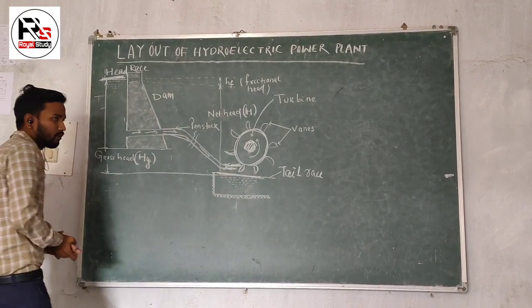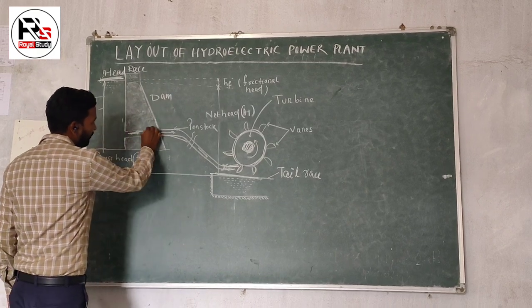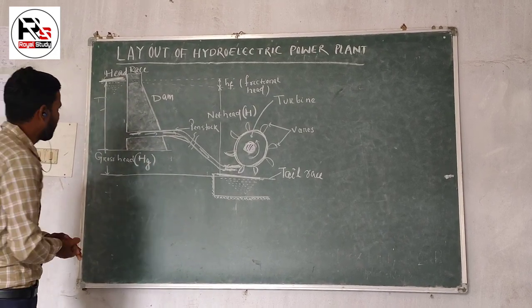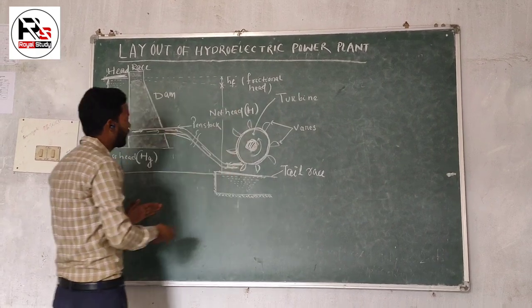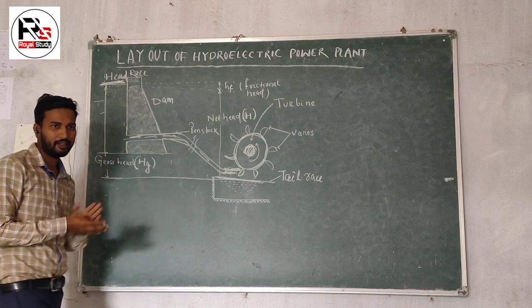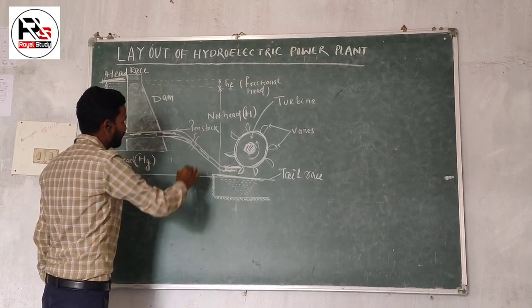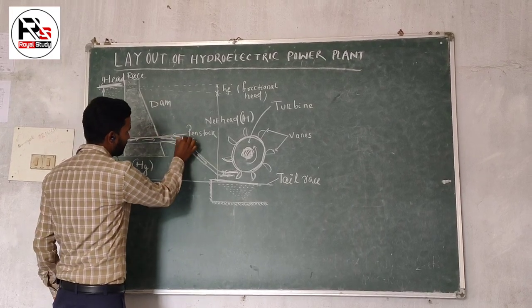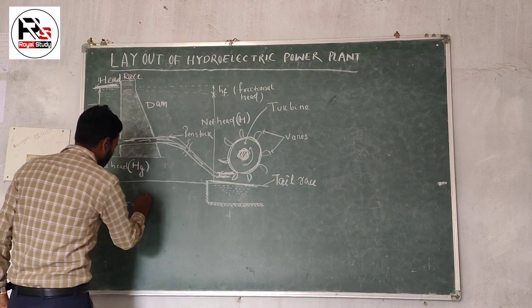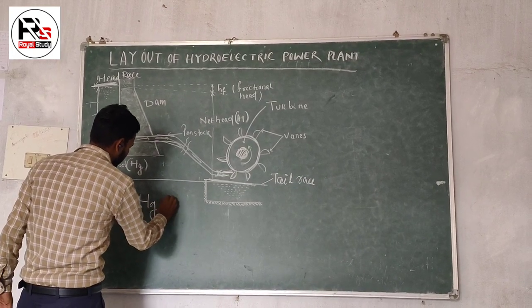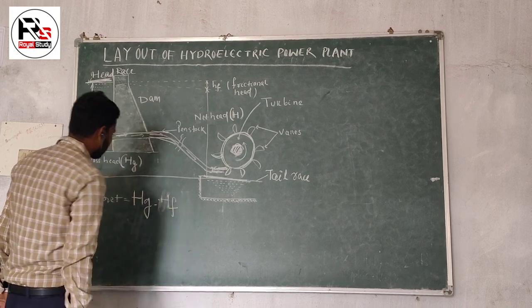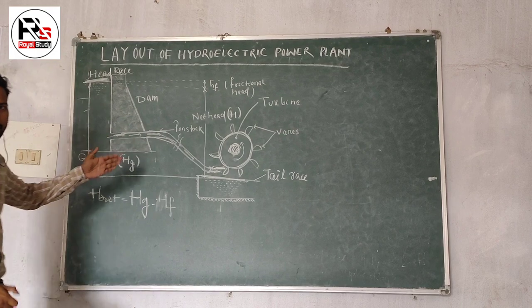What is gross head? When there is no flow inside the pipe, then the difference between the headrace and the tailrace — that is the gross head. And what is net head? When there is some water flowing inside the pipe, then there is some loss of head due to friction between the flowing water and the pipe wall, and also some head loss at bends. So net head is gross head minus losses. This is all about the hydraulics of a hydropower station.